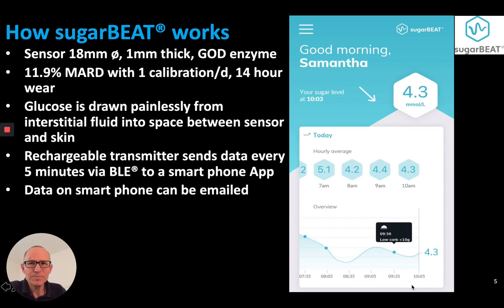How Sugar Beet works: the sensor is 18mm in diameter, 1mm thick, and has a GOD enzyme on it. The accuracy is 11.9% MARD with one calibration per day and a 14-hour sensor wear time. Glucose is drawn painlessly from the interstitial fluid into a space between the sensor and the skin. A rechargeable transmitter sends data every 5 minutes via low-energy Bluetooth to a smartphone app, as depicted here on the right. Data on the smartphone can then be emailed as a CSV or PDF file.